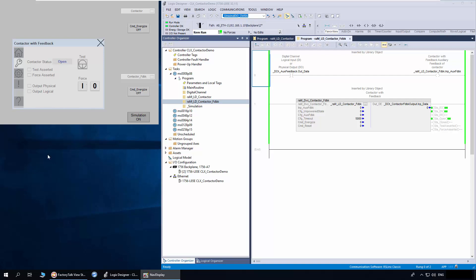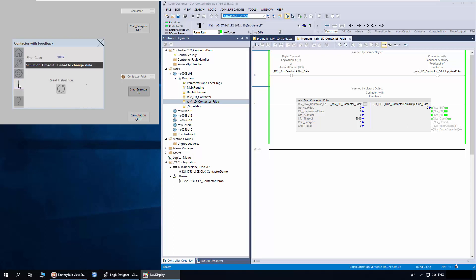To demonstrate the feedback fault, I will turn off the simulation so no auxiliary feedback is received. I will click the command button. The output is on, but since no feedback is received, the contactor status is still open. After timeout, the contactor has reported an error. The error description says actuation timeout, fail to change state. I will reset the command energize button now and reset the error. Once the fault is fixed, the contactor can be commanded again.